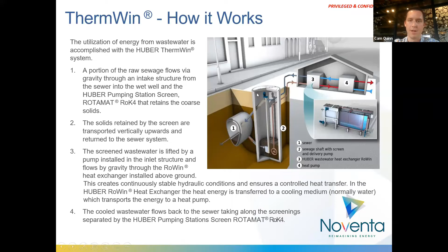And then the water returns by gravity back to the wet well where it mixes with the solids coming up the top of the ROK4 and goes back to the sewer. So essentially all we're doing here is creating a little sewage circuit that we heat up or cool down a couple degrees and then send it straight back to the sewer. On the other side of the RoWin heat exchanger, as we talked about on the previous slides, we have a chiller or a heat pump connected. And depending on whether we're heating or cooling, we're either connected to the evaporator loop or the condenser loop to extract or reject heat to the sewer. So that's how the system works from, we'll say, a system overview.